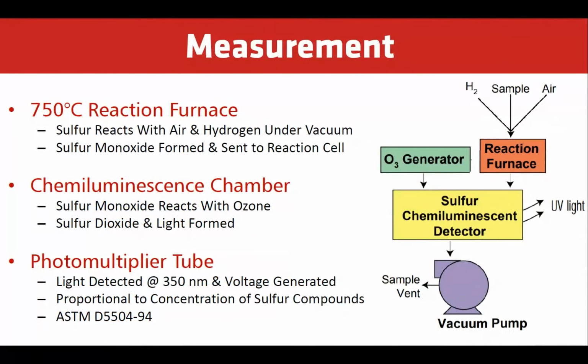The measurement. So basically, the reaction furnace, we operate at 750 degrees C. Sulfur reacts with air and hydrogen under vacuum. Sulfur monoxide is formed and sent to the reaction cell. Chemiluminescence chamber, sulfur monoxide reacts with the ozone. Sulfur dioxide and light is formed. The photomultiplier tube, light is detected at 350 nanometers and voltage generated, proportional to the concentration of the sulfur compound. And it falls under the ASTM method.